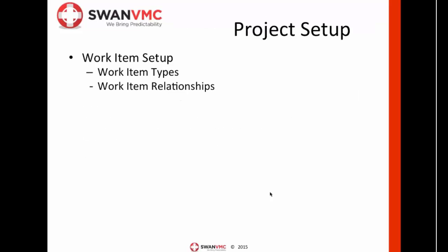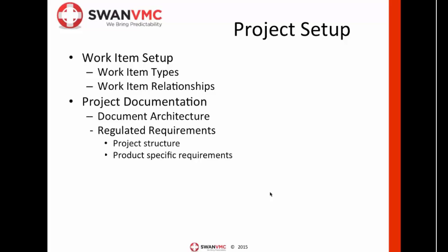So hopefully this whets your appetite to take a look at how to set up a typical medical device project. I typically break up the initial discussion into a number of general topics. The first is a discussion to define the construction of the project logic. And so this is typically communicated in a comprehensive traceability table. Later we'll discuss a template you could use as a starting point for your implementation if you like. At least it gives you a starting point so you can discuss it internally.